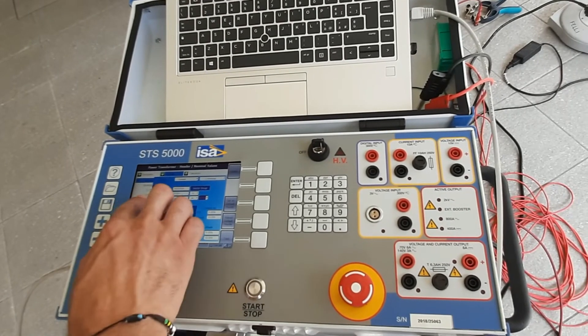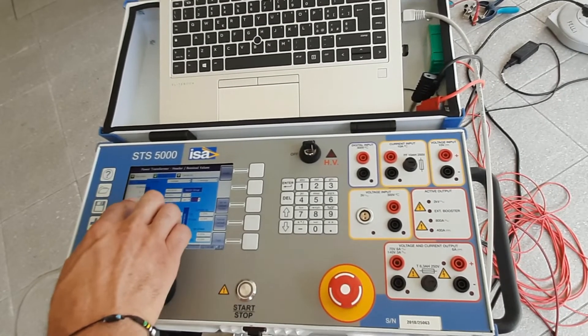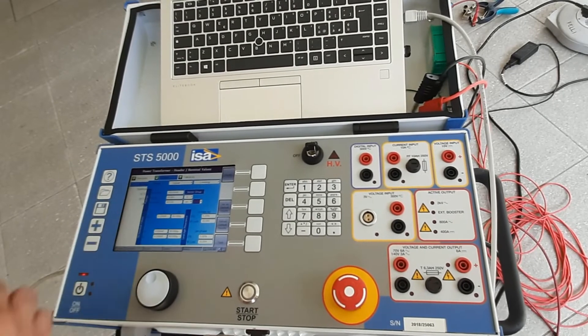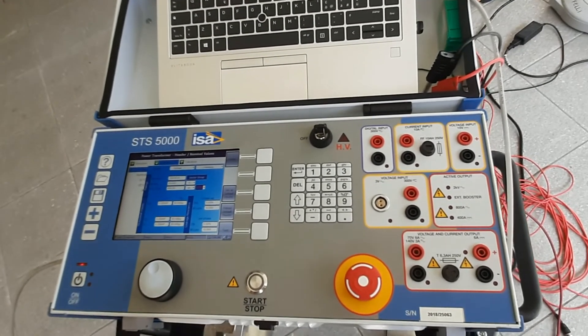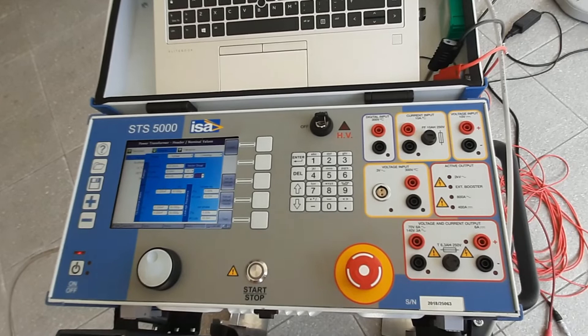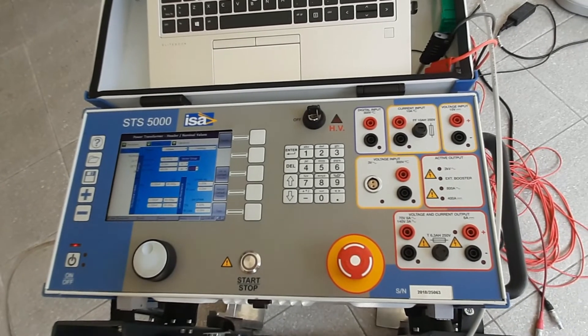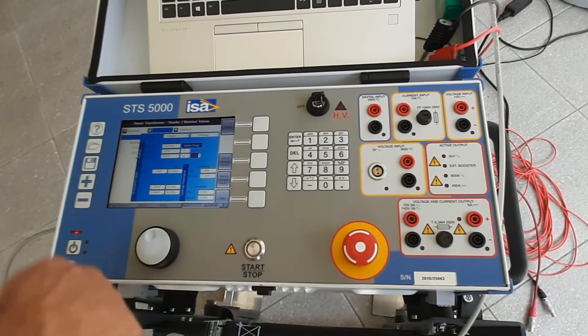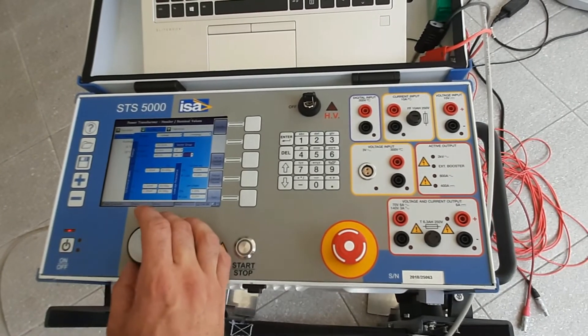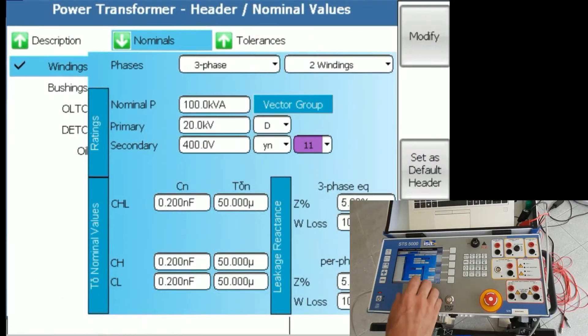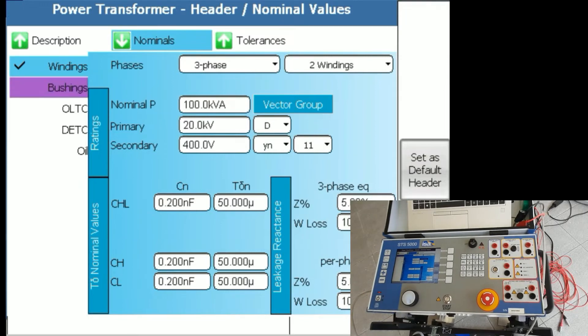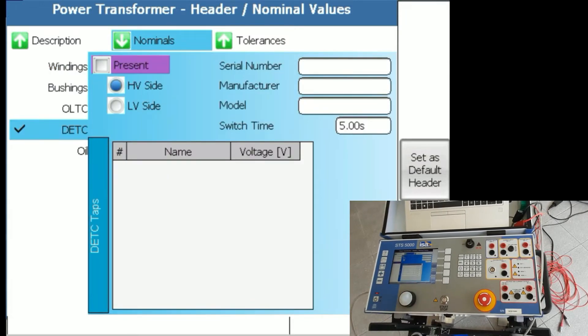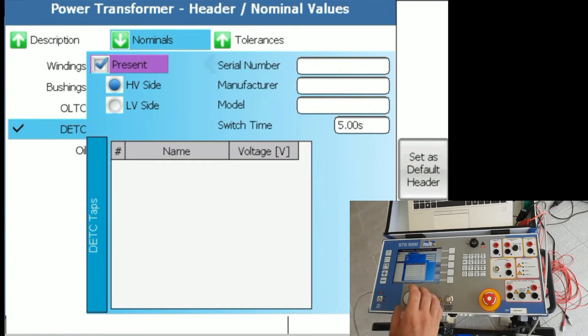In our case, we have a de-energized tap changer. The difference being on-load tap changers are more used on transmission transformers which have many positions of tap changer, 17, 25, 18, 19. De-energized tap changers have between three and five or six positions.